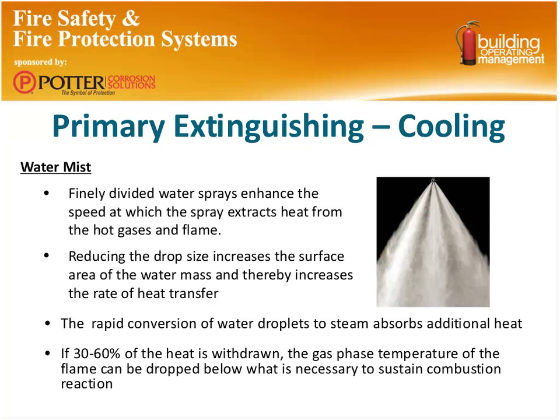They don't fall out of suspension as fast. What can actually happen is you kind of create an attenuation barrier to the potentially flammable objects around the fire source. So it just works in a little different method. 30–60% of the heat is actually withdrawn, and we create just enough steam that we can displace a little bit of oxygen from that point of combustion. So very similar, but in some ways a little different than the sprinkler system.